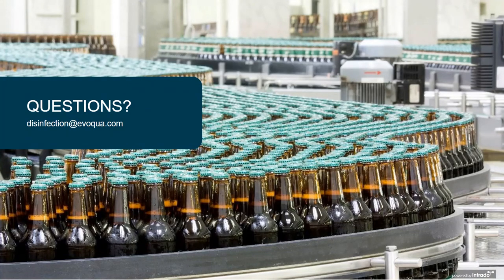All right, so one of the questions we received said, can UV technology be an alternative for water chlorination? I'll take that question. Very good question, thank you. Typically not, okay? So UV has no residual. So it can inactivate microorganisms at that point of use, but downstream there is no protection.